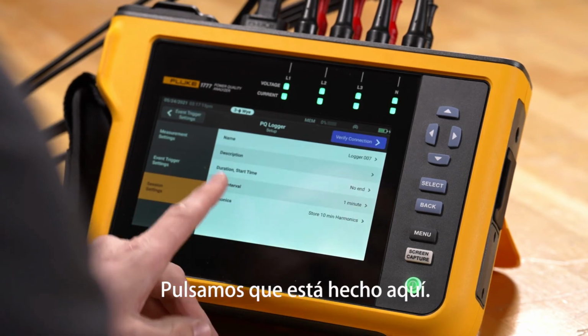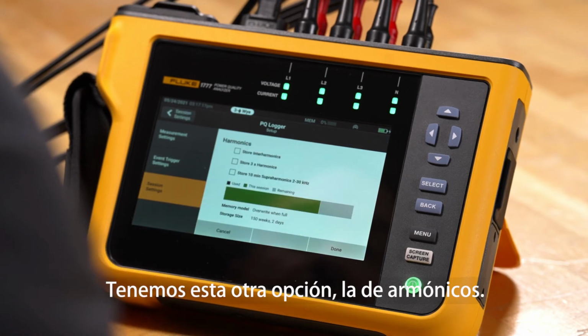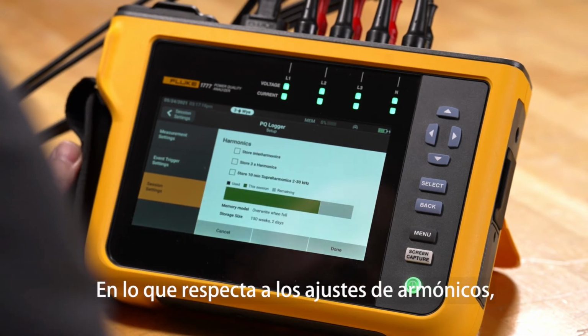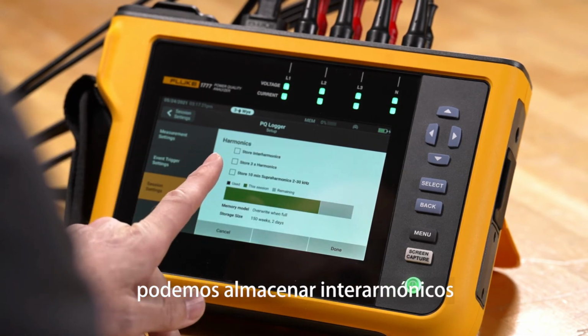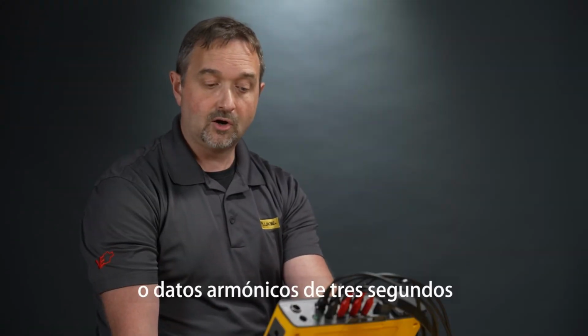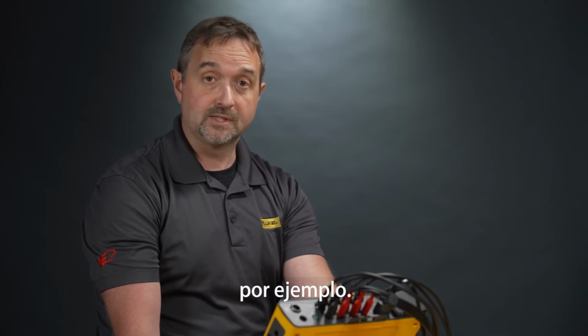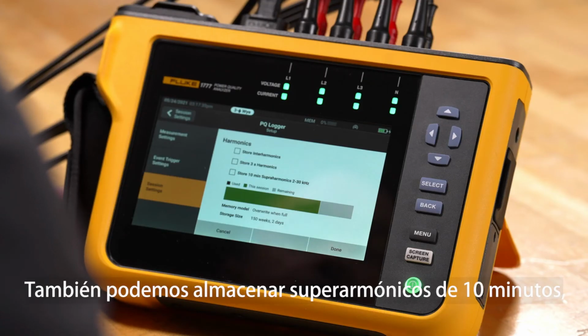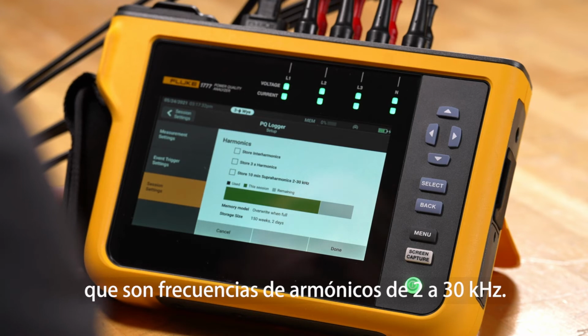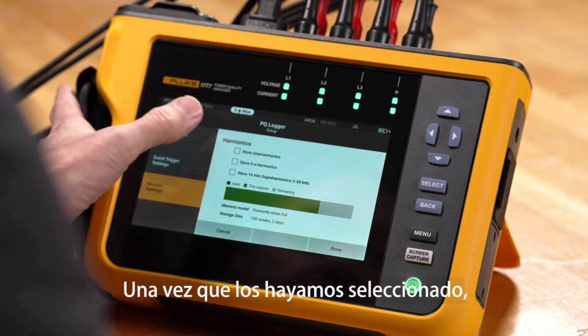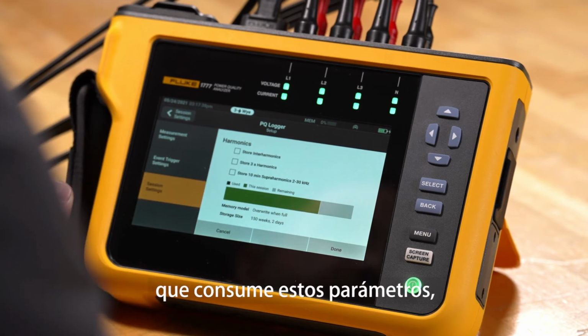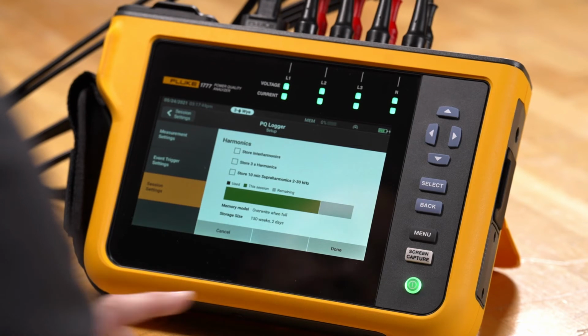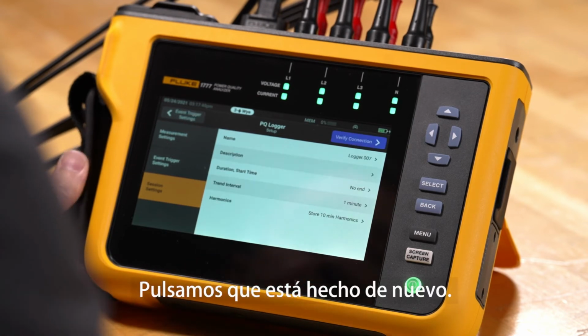We're done here. We also have an option here, harmonics. For harmonics setup, we can do store interharmonics. We can do 3-second harmonic data, which would be for IEEE 519 purposes as an example. We can also store 10-minute super harmonics, which are 2 to 30 kilohertz harmonic frequencies. Once we pick these, it'll also show us how much memory consumption is taking place from those parameters, letting us know the max record time. I'm going to tap done here.